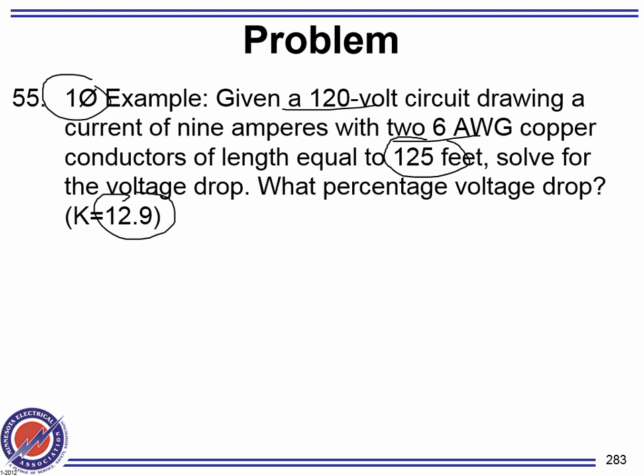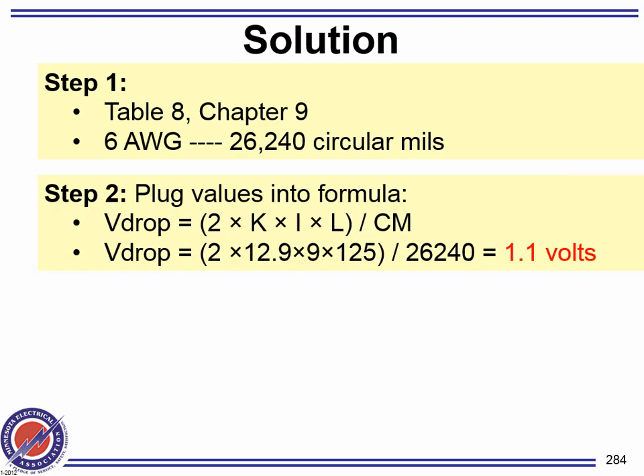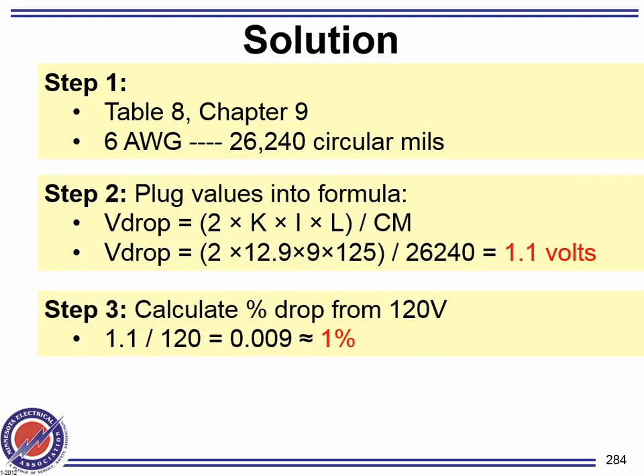Table 8, chapter 9. So the first thing you need to do, gentlemen, is go to table 8, chapter 9, and from table 8, chapter 9, you can find the circular mill, which is 26,240 circular mils.